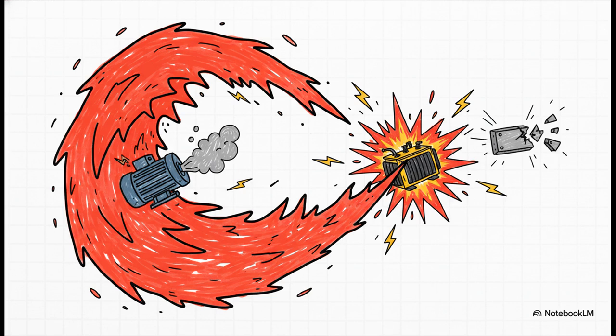Currents can skyrocket to 10 times their normal levels. You get massive voltage spikes that can puncture the insulation on motors and transformers. We're talking about explosive failures, blown capacitors, total system collapse. This is exactly why you can't just grab a filter off the shelf—it requires really careful engineering to get it right.